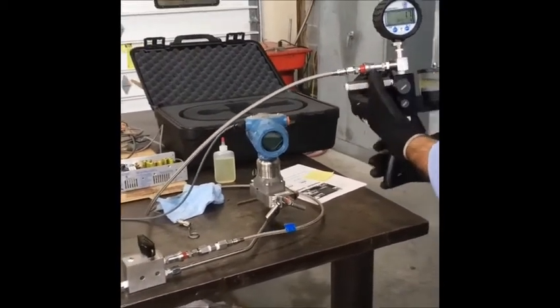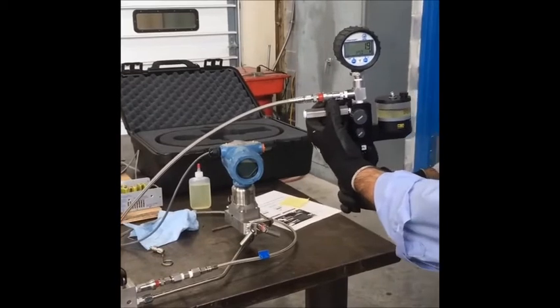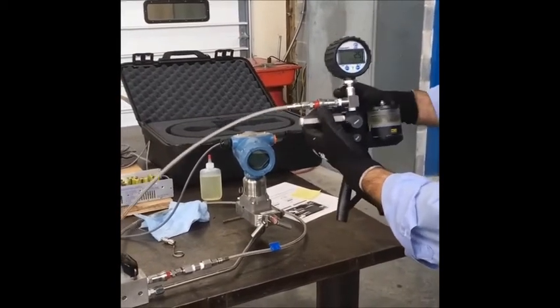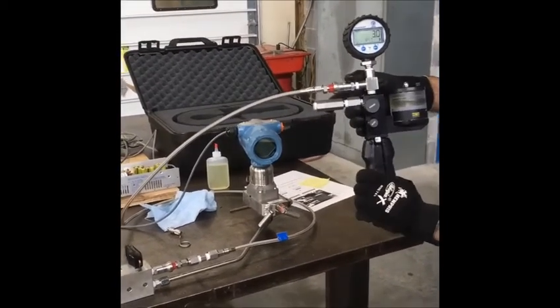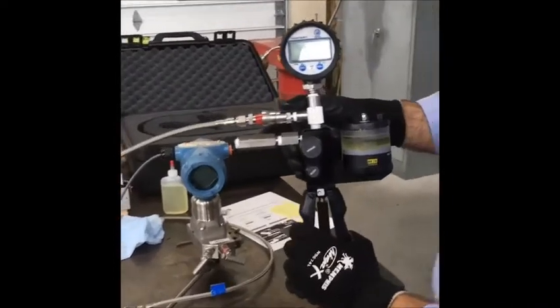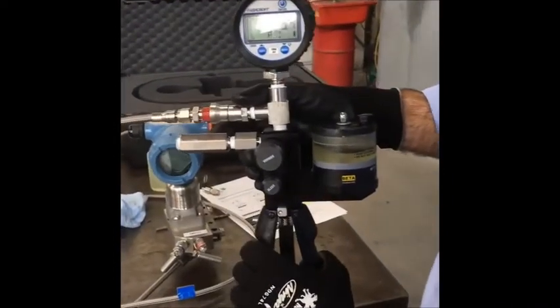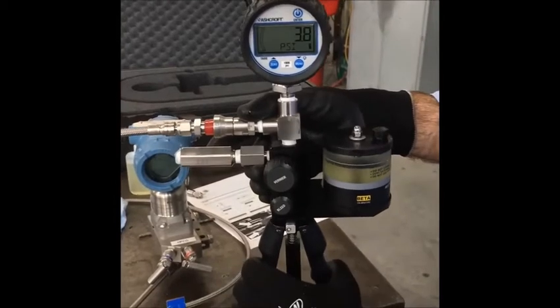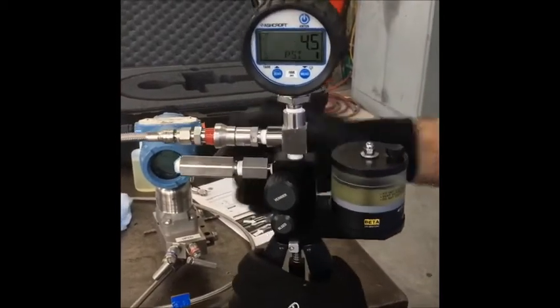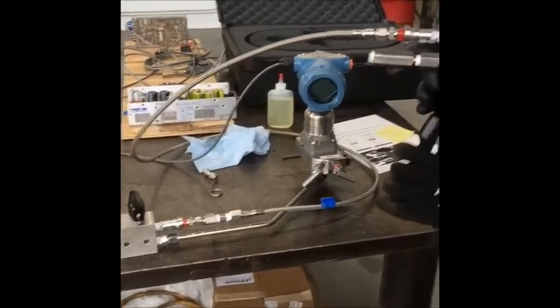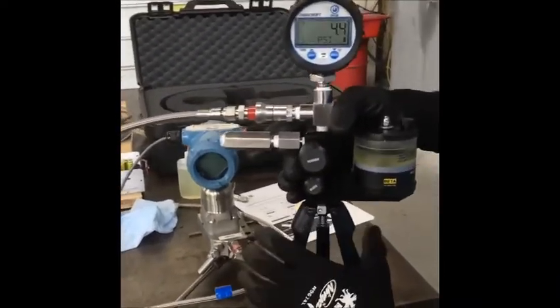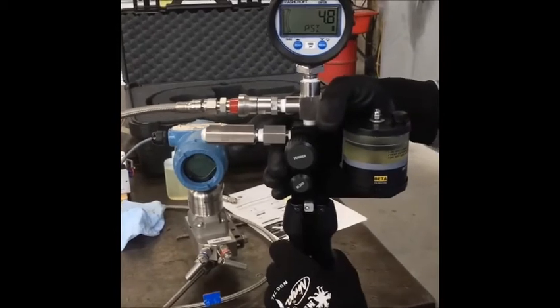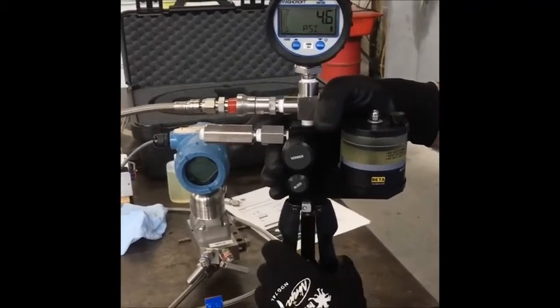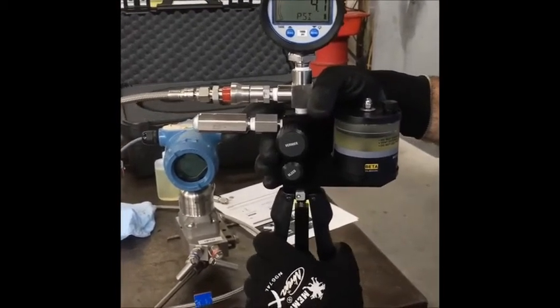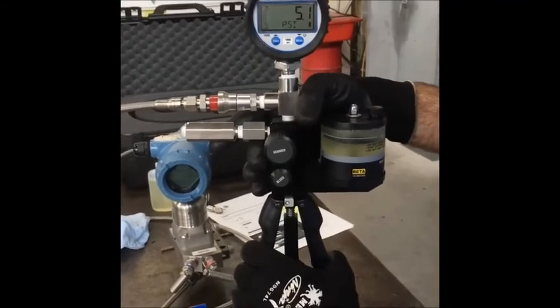So now once we're to this point, we can begin to pump on the pump. I'll turn it around this way so you can see it. And I will have to pressurize the lines that are involved. So that will also include, in our case, this line that's going over to the high pressure cutout. So we'll have to compress any gas that's in that line. Sometimes this can take a few pumps. It can take a little while. It depends on if the pump has been used before and if everything is all primed up.